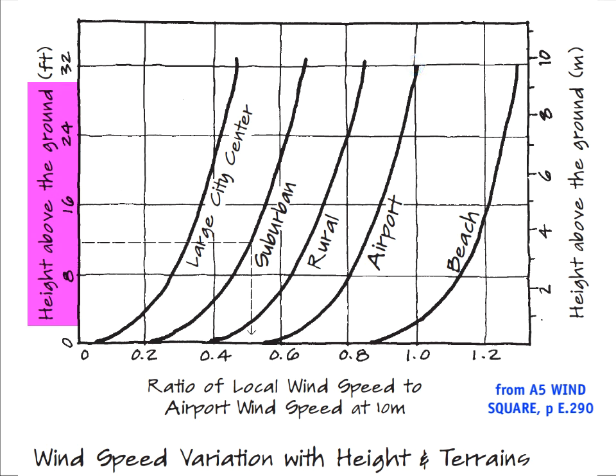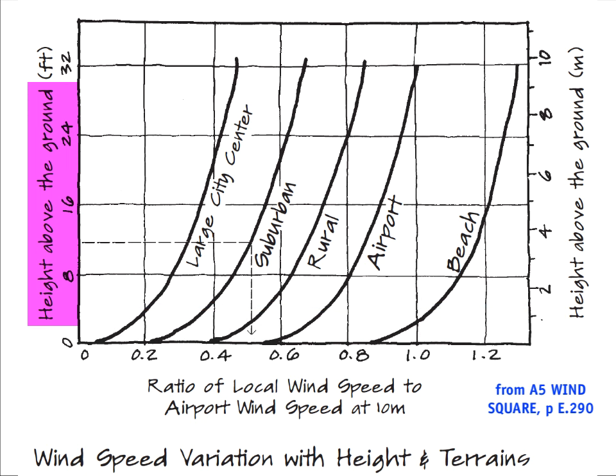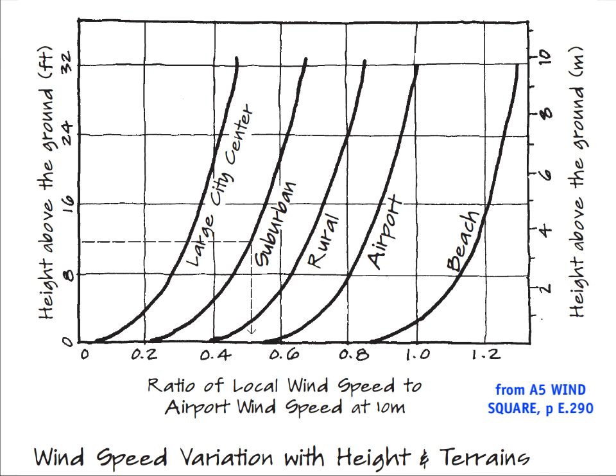Height above ground also makes a significant impact. A one-story building with windows around 4 feet up will have much less wind speed than at 10 meters above ground. Pick your location based on site context — small city can use suburban, large city center with high-rise buildings uses the large city center category. Then find the height corresponding to the average height of your inlets and outlets. For example, at about 12 feet above ground in a suburban location, the ratio of local to airport wind speed is about 0.5.